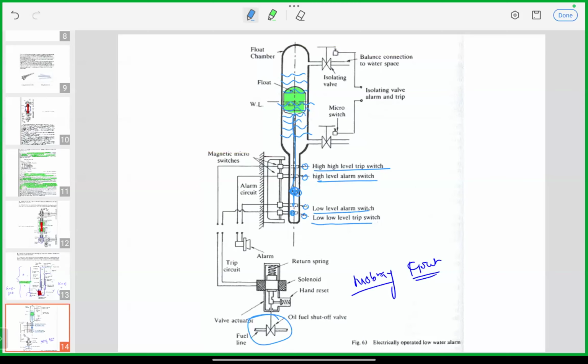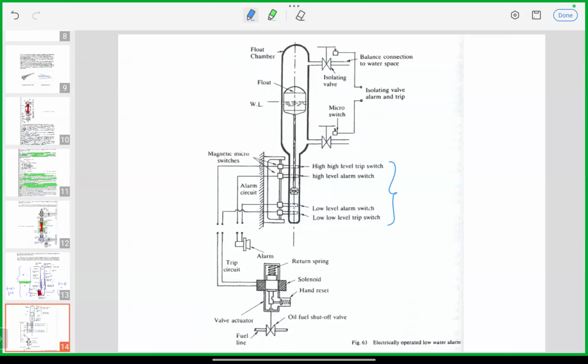But the problem with such a device is that if the float gets corroded, it will lose its buoyancy, and then it may not be able to give the correct indication of level. It will not be able to give the correct control. Low level alarm, high level alarm, and protection for your boiler may not be adequately provided. इसमें होल हो गया तो क्या होगा? It will lose its buoyancy. Isn't it?